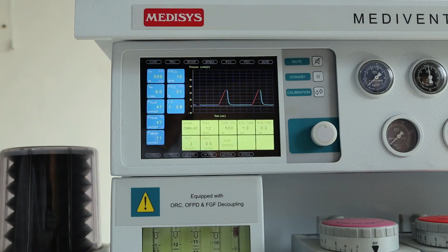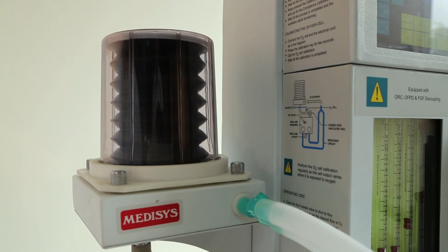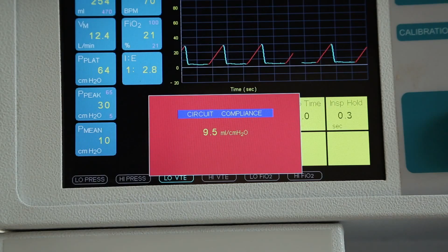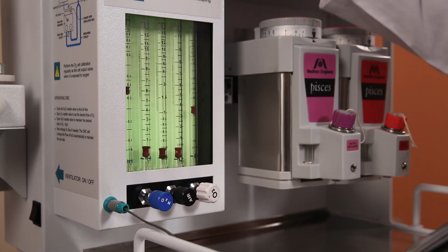This is also a very unique thing. You know that every part of the machine, the breathing circuits and all, they have their own compliance, and then they may change with the flow, they may change with the size of the tubings, and this machine automatically calibrates the flow according to the compliance. Another safety device is the oxygen failure protection device here and the oxygen ratio controller.